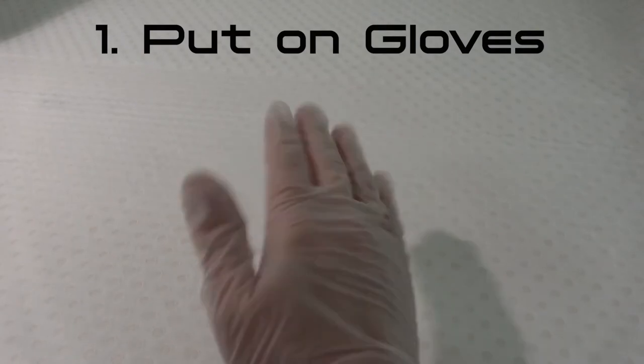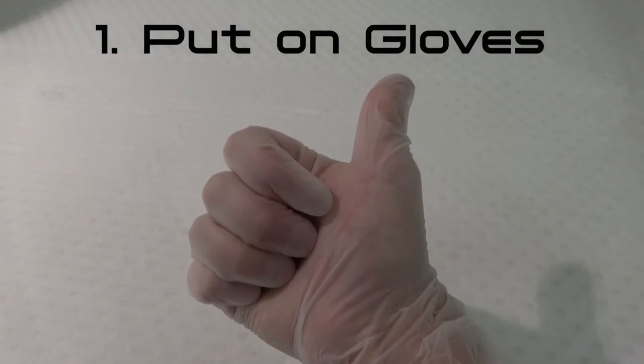Preparation. Step 1: Put on gloves. Always keep fingerprints off anything that will go into the SEM chamber such as stubs and samples.